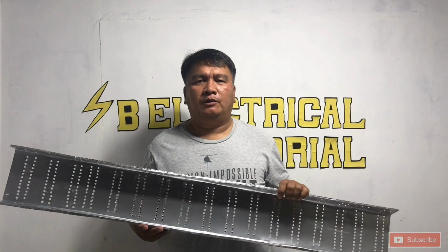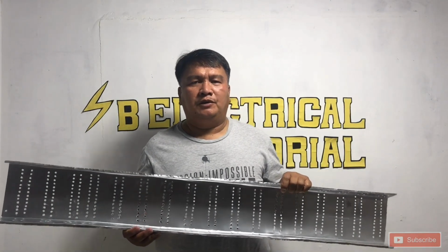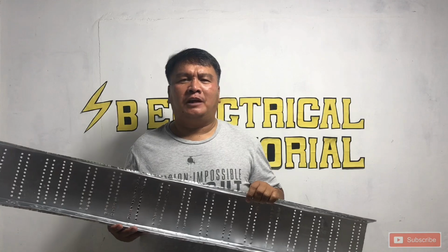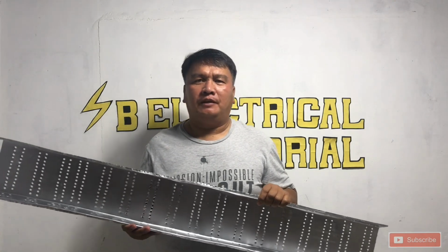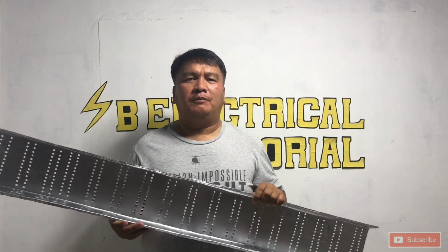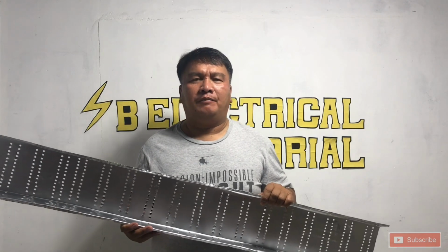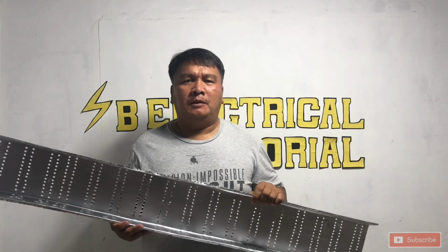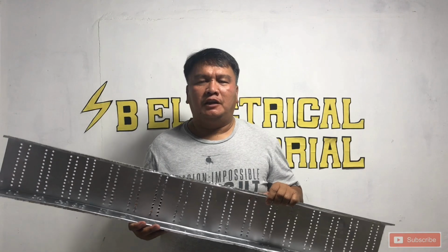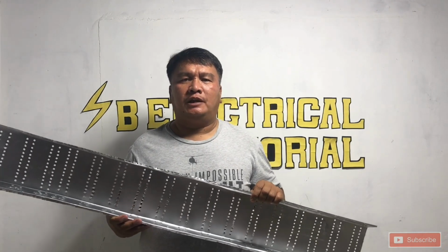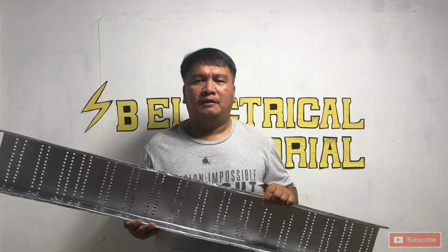Now let us go to the formula for this cable tray. The multiplier I always use is 0.8. Any size of the cable tray, cable ladder type, or cable trunk, multiplied by 0.8, then divided by 2 - the result is the equal measurement to be cut on both sides.